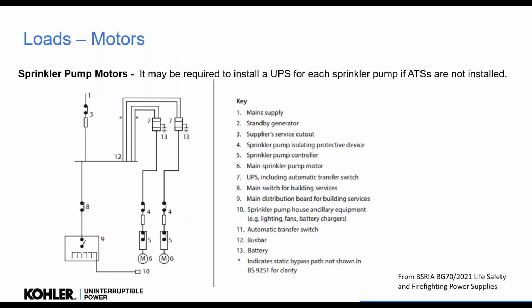Some loads, like sprinkler pumps, the regulations are catching up. Sprinkler pumps can be fed from individual UPSs, and this is where we don't need an ATS at the end, because we've got one UPS, one pump. So if the pump has a problem, the UPS has a problem, we just use the other one. Different regulations will require different things, but this is where we need them to catch up.